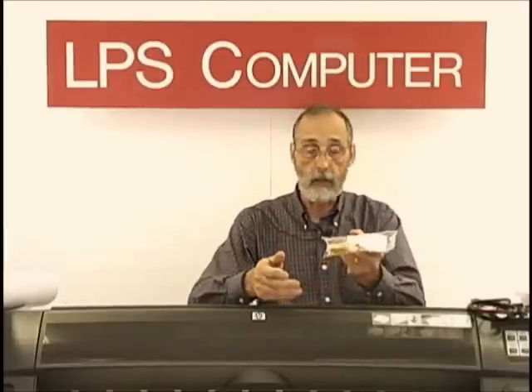The kit has non-evaporating oil. This is an important detail because you need the friction to stay the same left and right in the carriage motion. When the machine does a y-axis calibration, it measures the friction left and right and does a voltage offset for the motor to get those speeds exactly the same in both directions. If at some point the friction changes, you start to see zigzag in your output, and that's not a good thing. So you want something that remains constant, and non-evaporating oil will do that. A spray-on oil will actually get sticky as it evaporates and work against you. So it's an important little detail, nice thing to have.